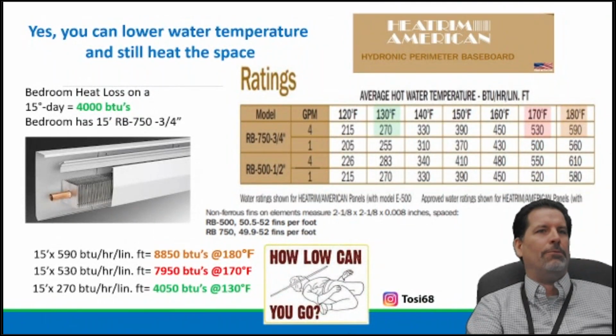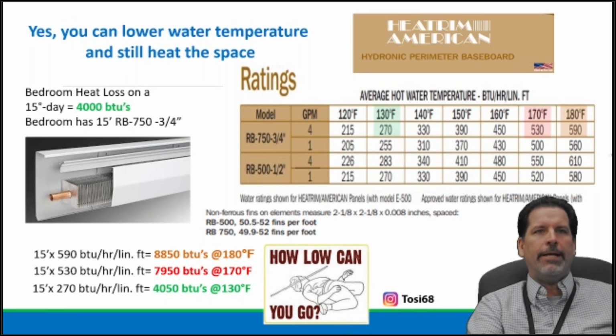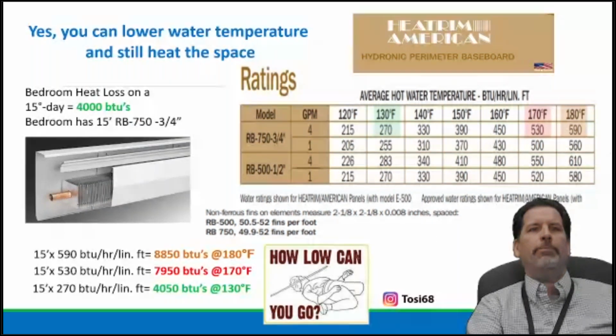Map out your own home, measure elements, look at your own space if you have the opportunity. Because when you become a believer and you hear the system, on a mild day, like the past couple of days on Long Island with winds and chilly weather, we had some snow north of us. You would hear your boiler turn on, turn off. That's an indication it's way oversized, or how come it's short cycling and it's a condensing piece of equipment?